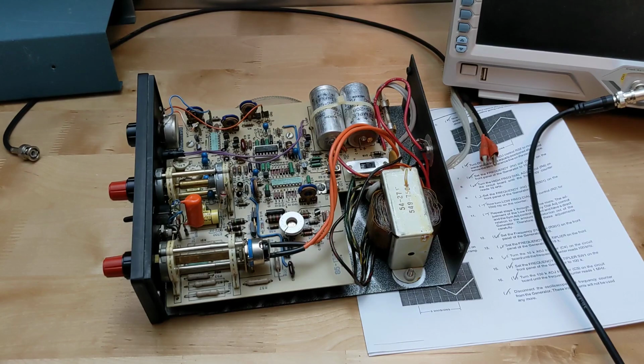While performing the calibration, I observed that this unit doesn't have any trim pot for adjusting DC offset. The design must have changed from what was documented in the version of the manual I have. There was one other mod or repair made. A resistor has been paralleled with another. R42, an 18K resistor, has had a 56K resistor connected in parallel to it. While the electrolytic and tantalum capacitors in equipment of this vintage can fail, I tested them for value and ESR, and they were good, so I didn't replace them.